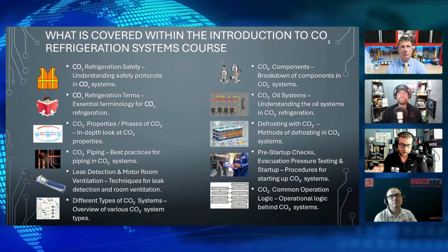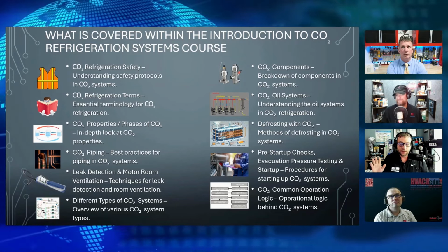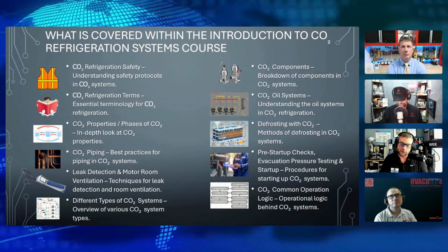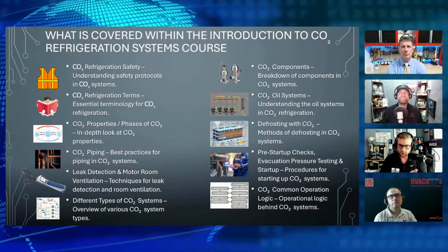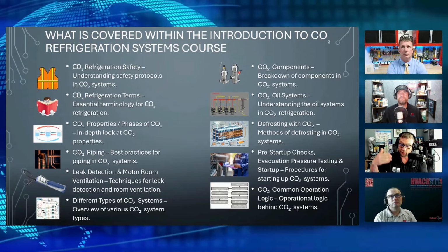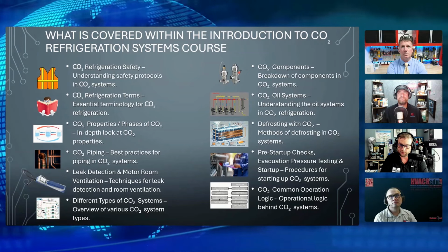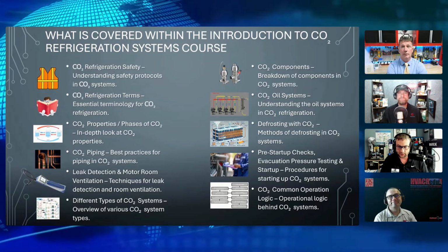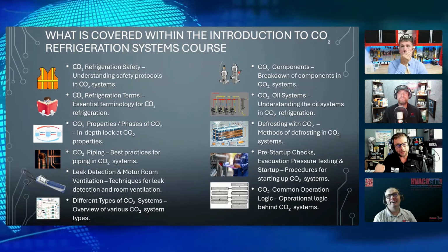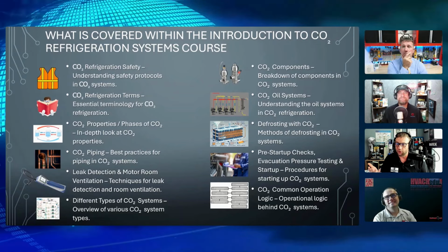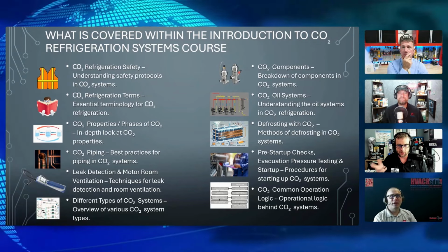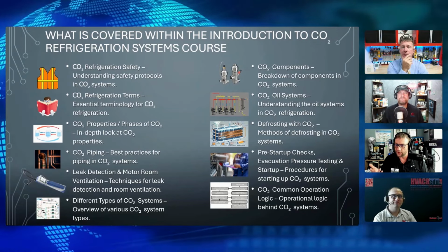Going into the suction, right? So that's, I don't have a calculator, so I'm not going to do it. Compression ratio, yeah. It's a very low compression ratio. And then on your medium temp side, you're going from 420 upwards of potentially 1,450 pounds, 1,500 pounds. Exactly. A lot of work on a compressor. But not really. If you did rough math, it was three and a half to one. Really not that bad.